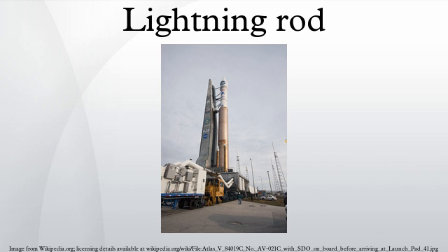As a result, at a few centimeters above the tip of a 20 mm diameter blunt rod, the strength of the field is greater than over an otherwise similar, sharper rod of the same height. Since the field strength at the tip of a sharpened rod tends to be limited by the easy formation of ions in the surrounding air, field strengths over blunt rods can be much stronger than those at distances greater than 1 cm over sharper ones. The results of this study suggest that moderately blunt metal rods are better lightning strike receptors than sharper rods or very blunt ones. In addition, the height of the lightning protector relative to the structure to be protected and the earth itself will have an effect."